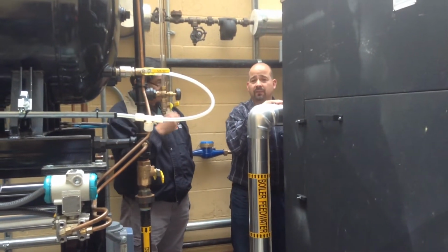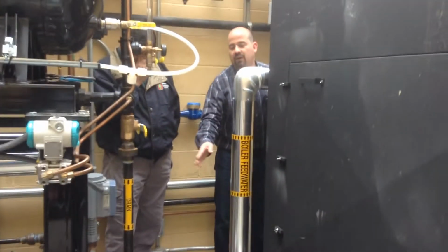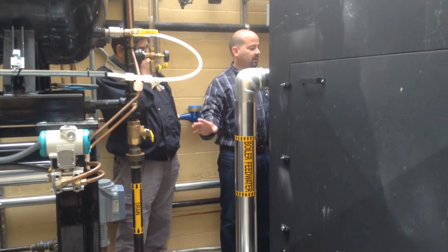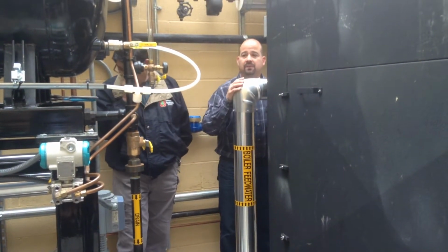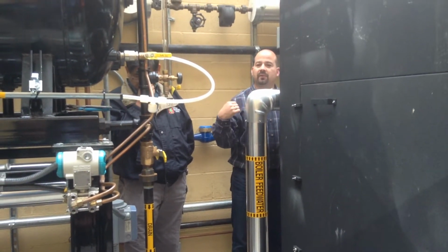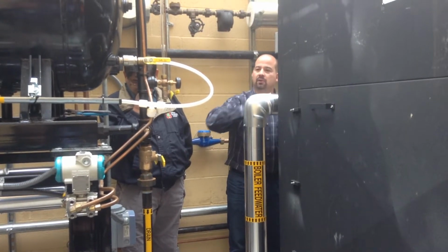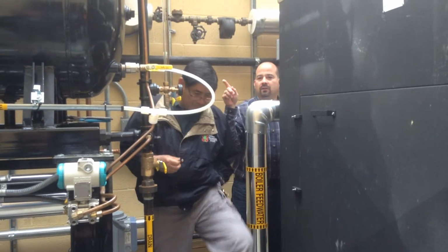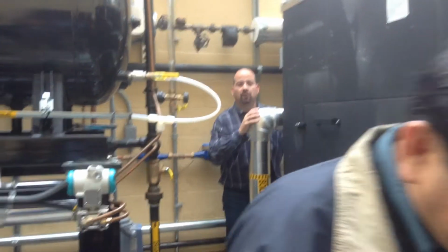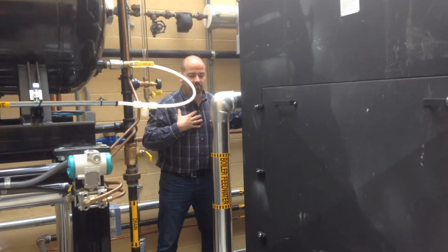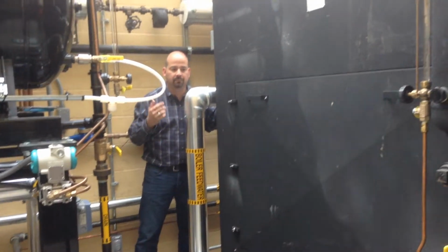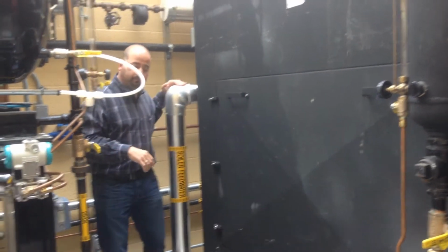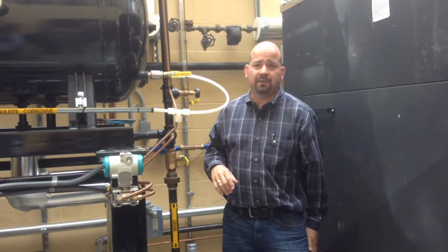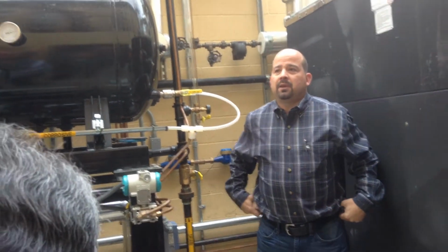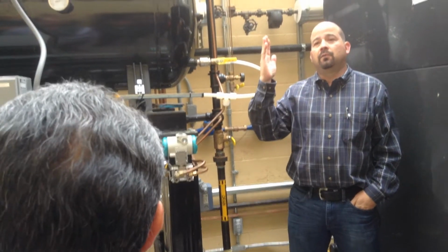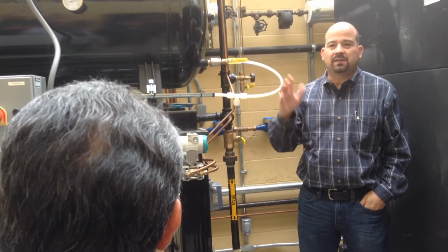We like to use these solenoid valves because normally you have check valves on the discharge of the pumps, but sometimes the check valves leak, they don't seat 100%, so we get steam that comes back from the boiler, and it works its way back into the deaerator, and it overpressurizes the deaerator. So we typically use the solenoid valve as a standard to prevent that from happening. What should the max pressure of the deaerator be? The safety relief valve is set for 15 psi. Deaerators can be anywhere from 0 to 5 psi, sometimes 8 psi.